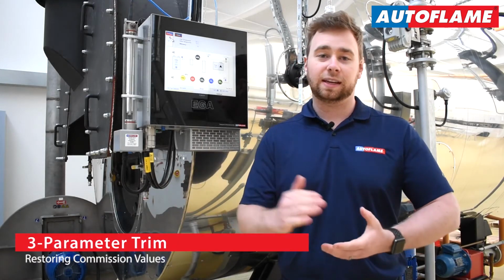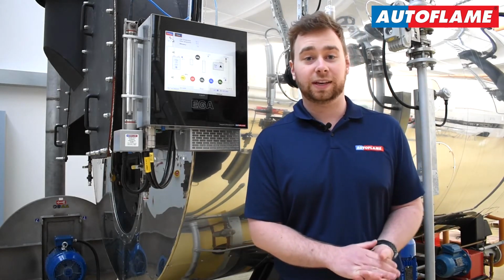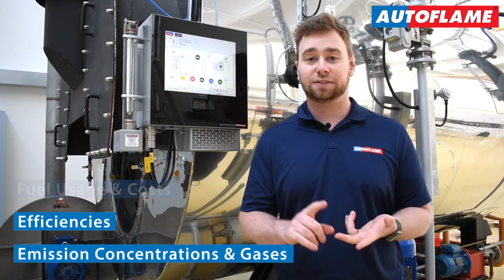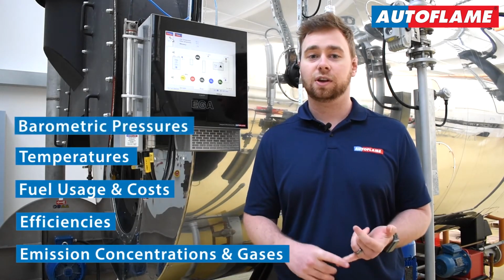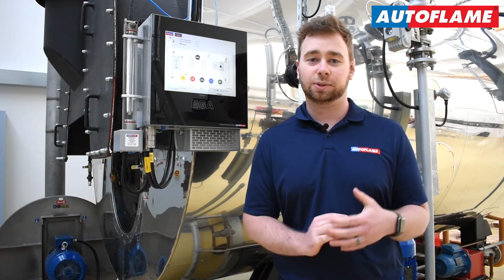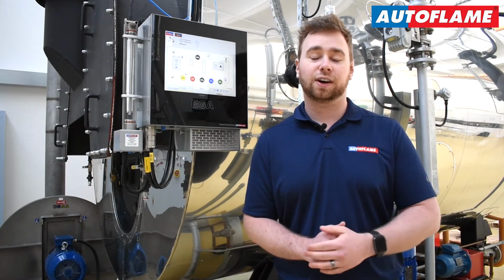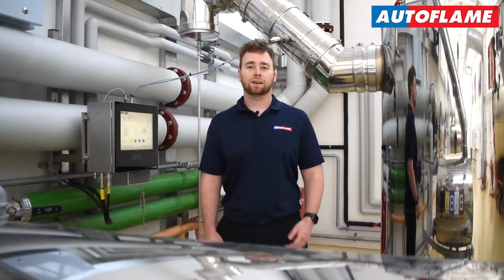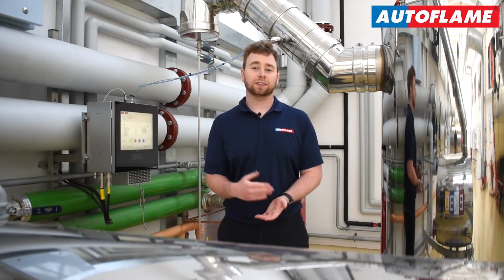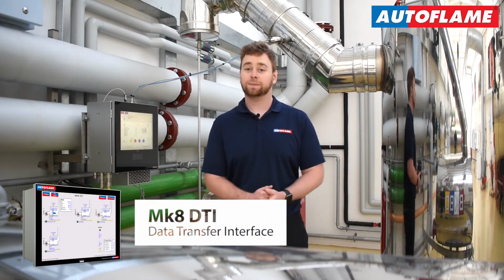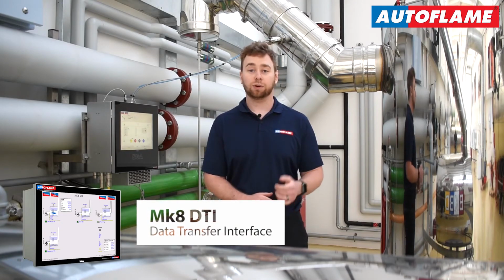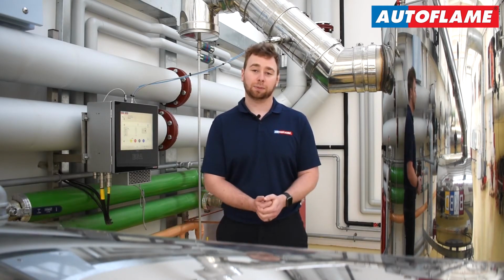Now, whether you've got the EGA in standalone mode or coupled with a controller, combustion data such as emissions, concentrations of gases, efficiencies, fuel usage, temperatures, pressures, all of this can be extracted into a CSV file for user-definable time periods. The EGA can also be integrated with our data transfer interface, the DTI, which we'll cover in a later video, for more advanced Modbus and data logging capabilities.